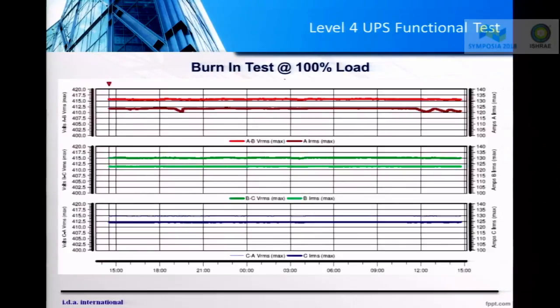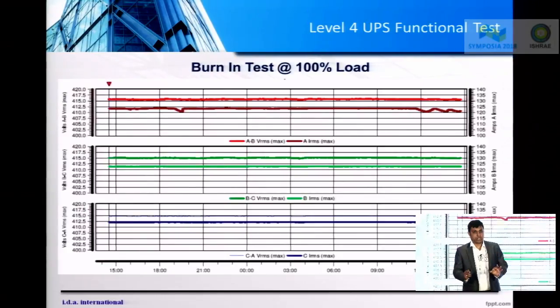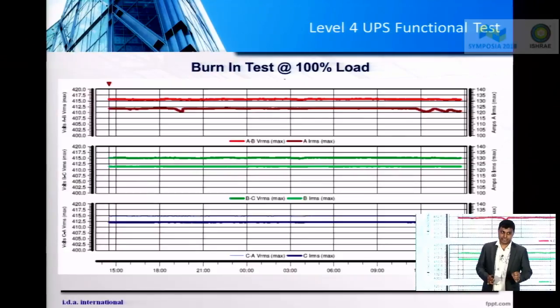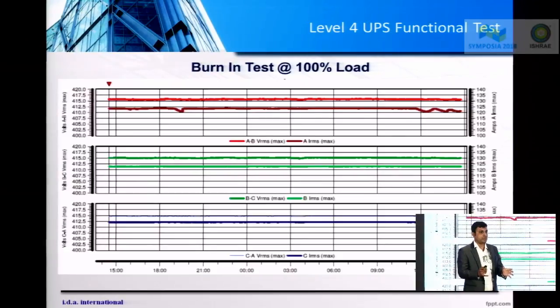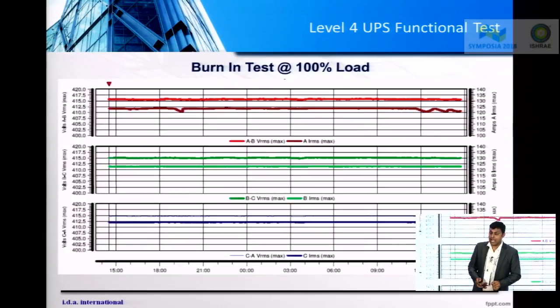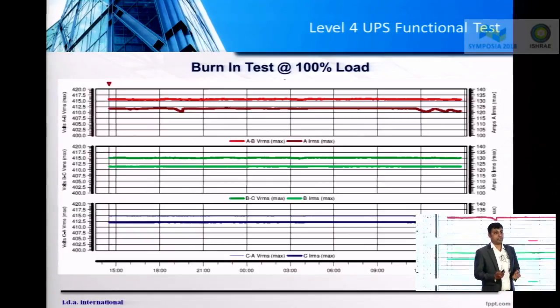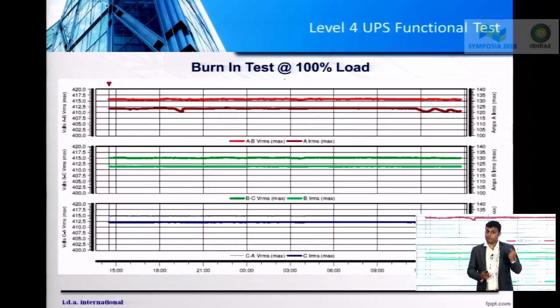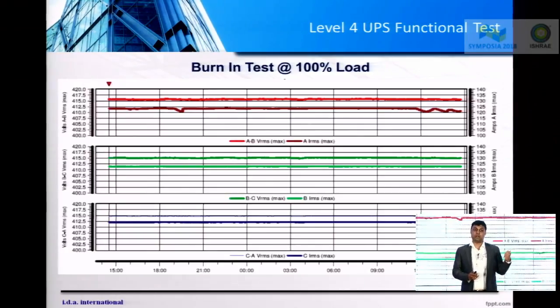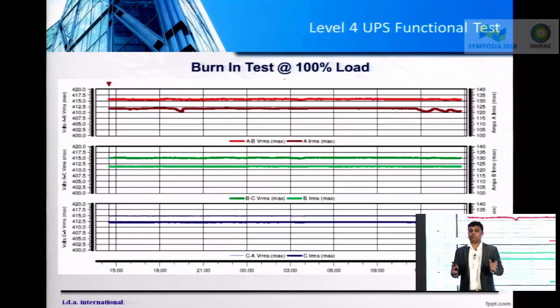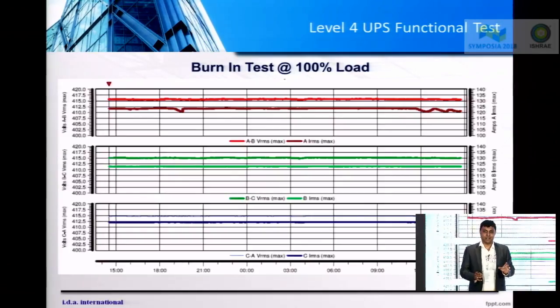Then comes the burn-in test, which is the most important or critical test for a UPS. You have to load the UPS to its maximum capacity and run it for certain hours. We can run it for 4 hours, we can run it for 8 hours. With my practical experience, what I've observed is the major failure of UPS could happen during this burn-in test. Out of 50 UPS, at least one could fail.